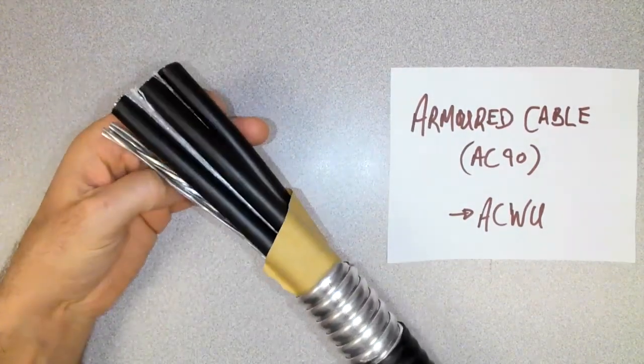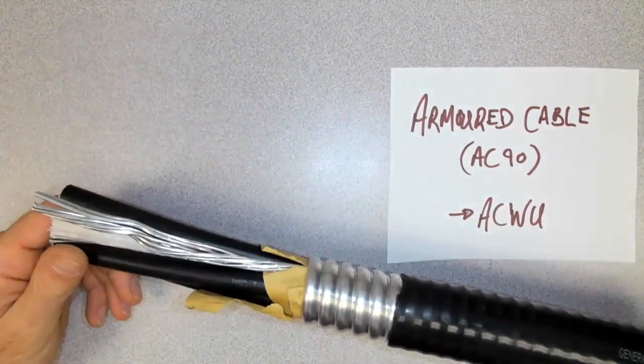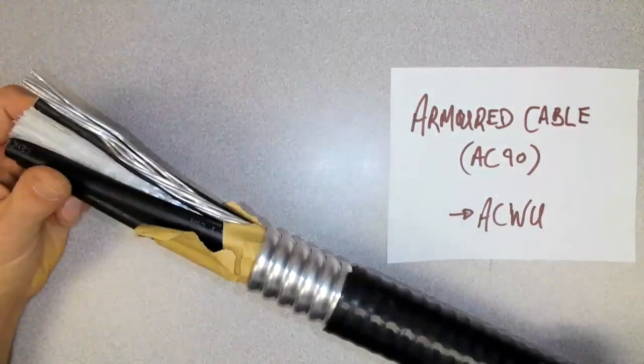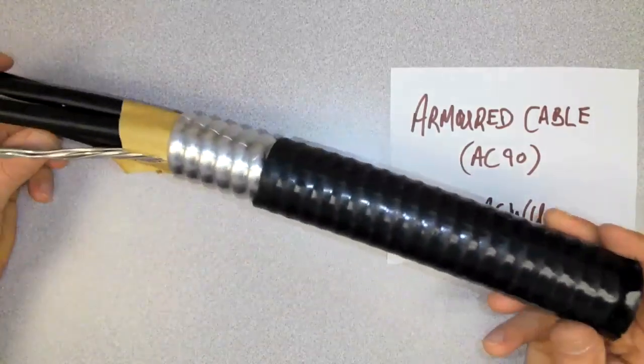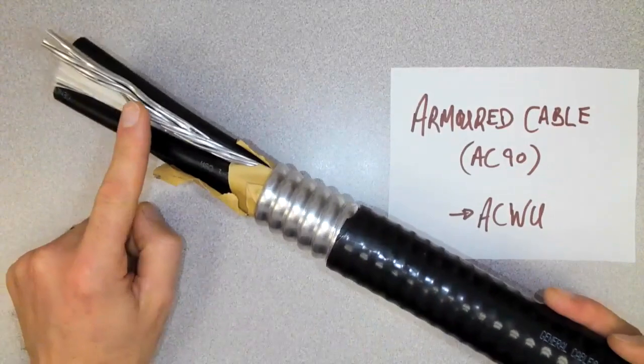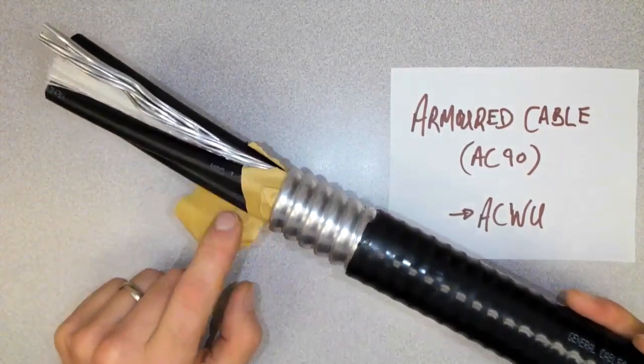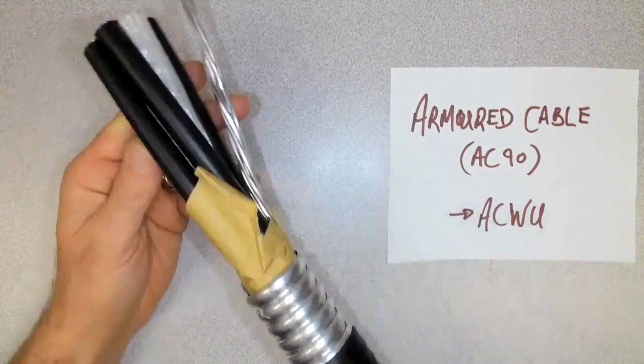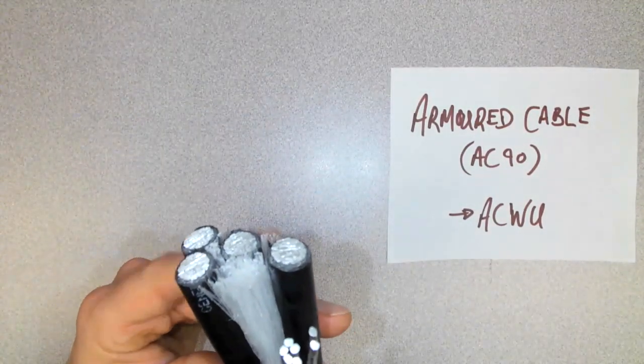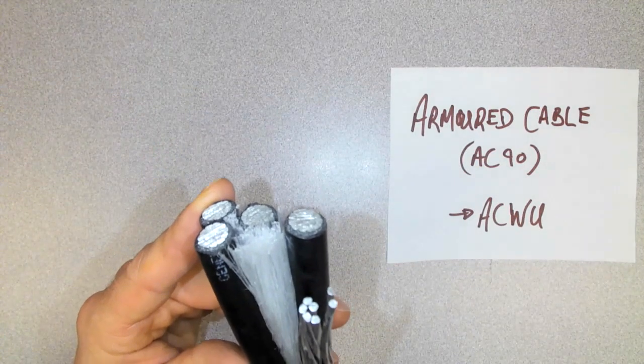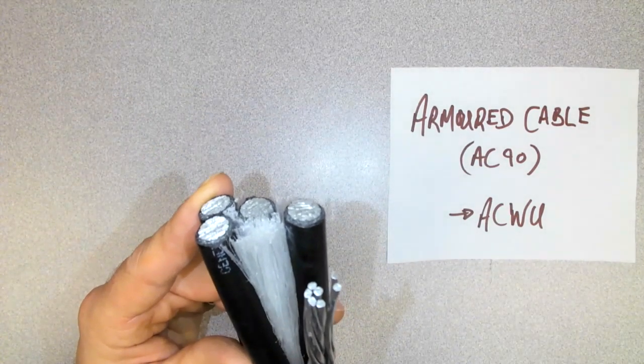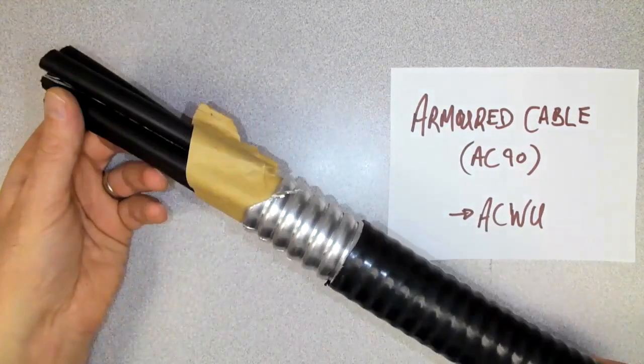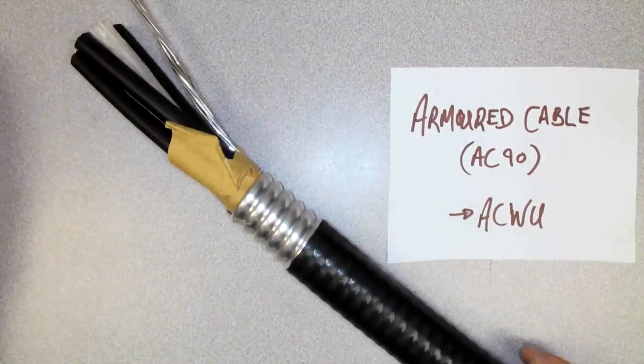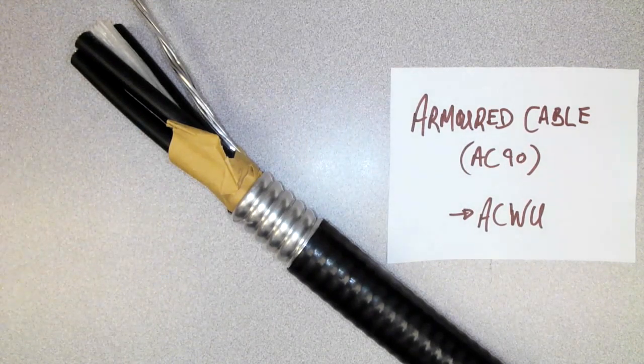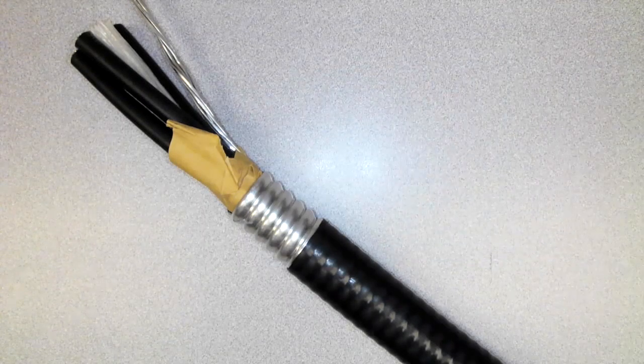This is ACWU. Now, ACWU, for individuals that are not really observant, would say it looks pretty much the same as TEC, and it almost does, except for the lack of inner rubber jacket. There's usually a paper or plastic liner to it, and in addition to that, ACWU is only manufactured in aluminum. So a substantial reduction in cost, however, it can't be used in every single installation that TEC would have been. So there is a difference between the ACWU and TEC armored cable.